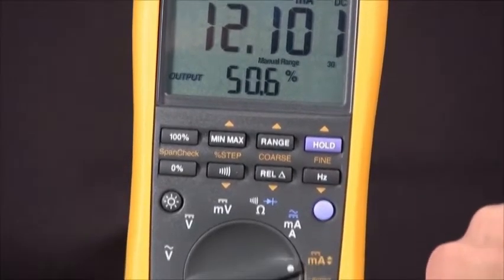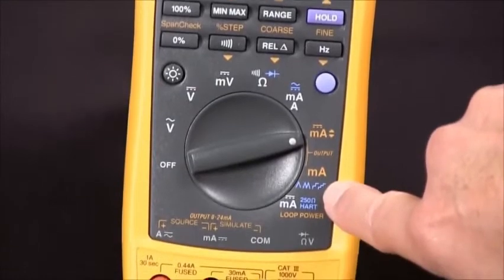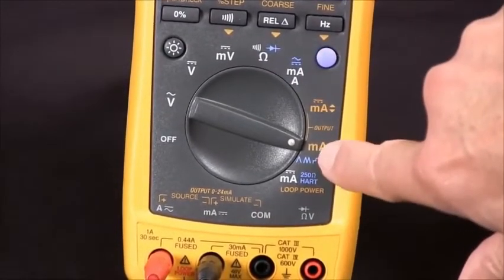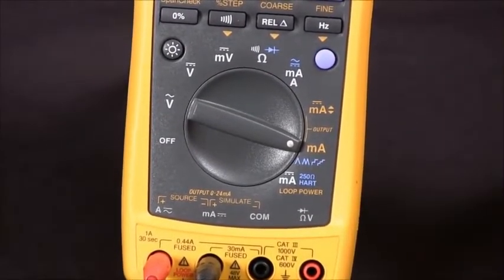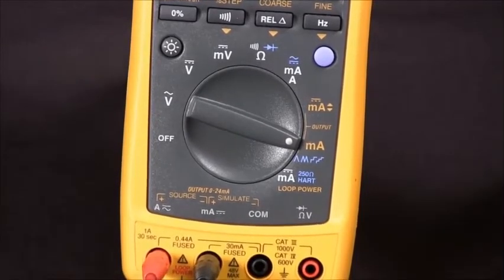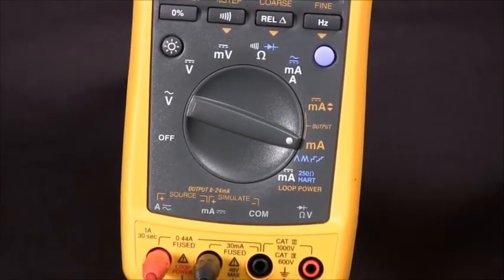If we need to do automatic ramping or step functions, we can go to the other sourcing position and with the blue key select one of those four. That's how we source 4 to 20 milliamps DC with our 789 process meter.